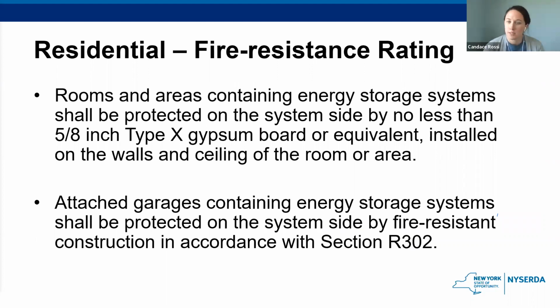For indoor residential systems, rooms containing energy storage systems shall be protected by a fire resistance rating of 5/8 inch Type X gypsum board or equivalent installed on walls and ceilings. Attached garages are to be protected on the system side by fire resistant construction in accordance with the code, which is basically a 1 hour fire resistance rating from exposures on both sides. If there is an incident, which is not very likely, you want to make sure the fire resistant construction is in place so it won't spread.